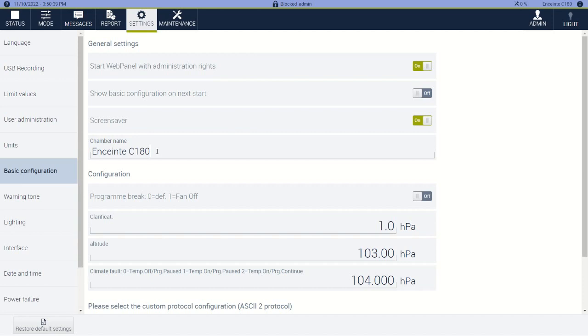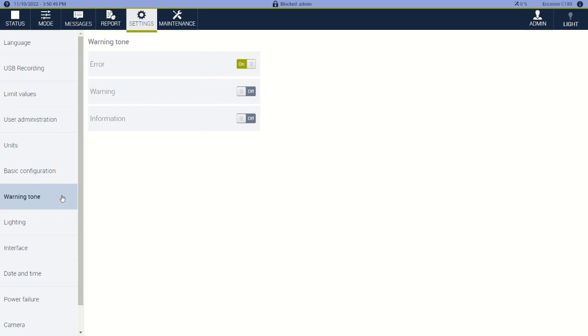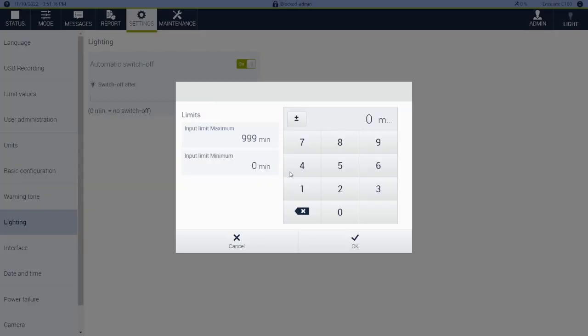For basic configuration, you can set the chamber name and different items up at the top, with some more features down at the bottom. The warning tone is the audible alarm from the WebPanel — you can set when it turns on and off. For the chamber lighting, you can set if it automatically switches off at a set period of time, or set it so that only the light button up in the upper right can turn the chamber light on and off. We'll set this back to 10 minutes.